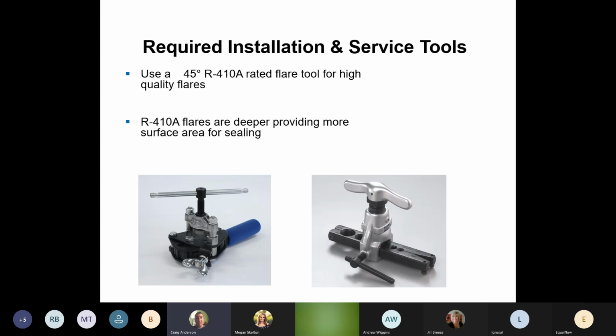Flaring tools, big thing. You can buy flaring tools out there that are not 45 degree, R410 rated. If you're doing a lot of flaring, make sure you have the proper flaring tools. You can get them at Canadian Tire and Princess Auto and stuff like that that are not rated for a 45 degree flare. The refrigeration on our mini splits and stuff like that take a 45 degree flare. So if you're running into a lot of leaks on mini splits and stuff like that, check your flaring tool, make sure it's proper, and you're using it properly.